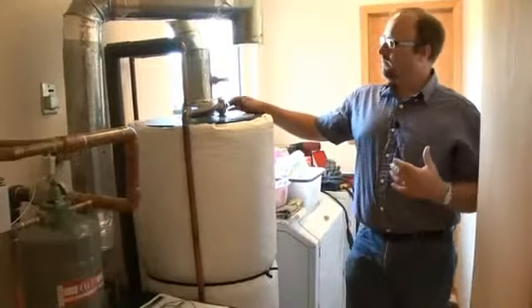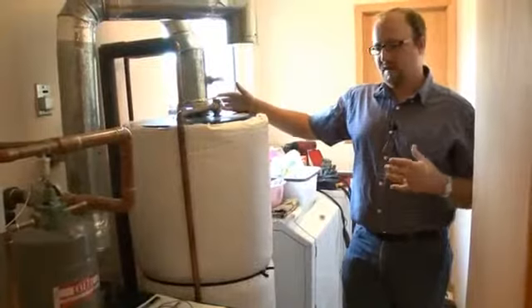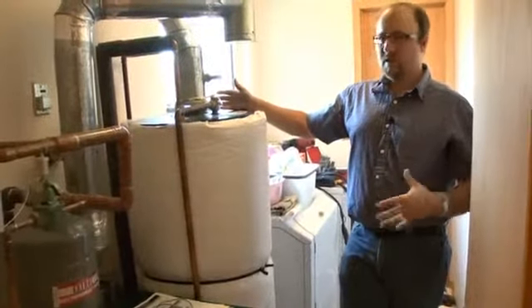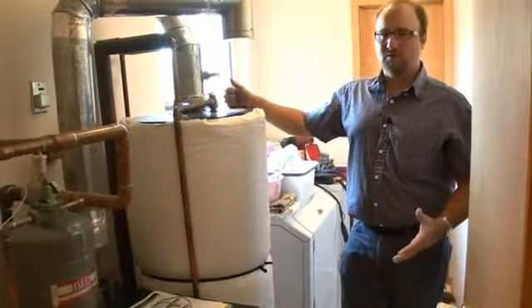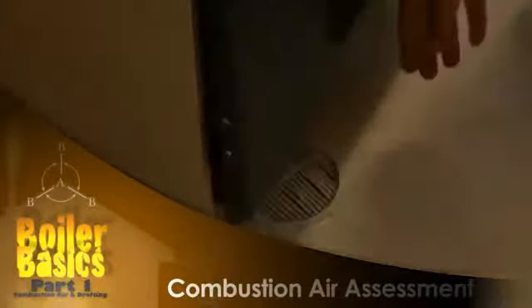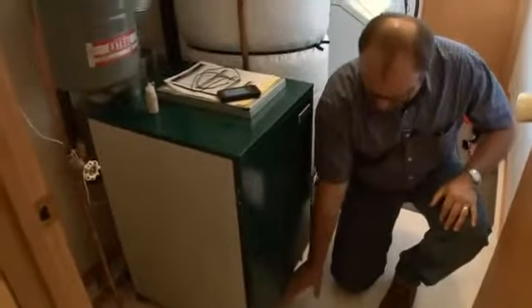Okay, so we have a little bit of a problem with our worst case combustion air zone. It comes down to we don't have proper combustion air to this room. This little combustion air right down here just doesn't cut it. This goes to outside, but it's low.